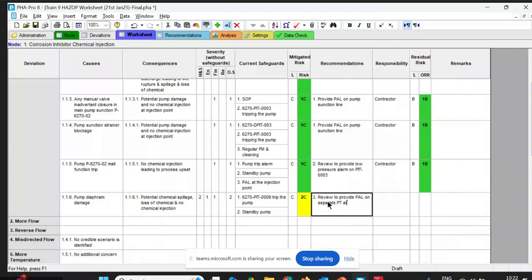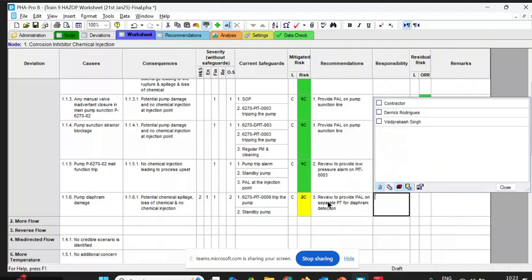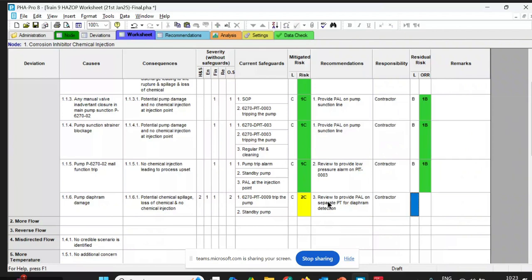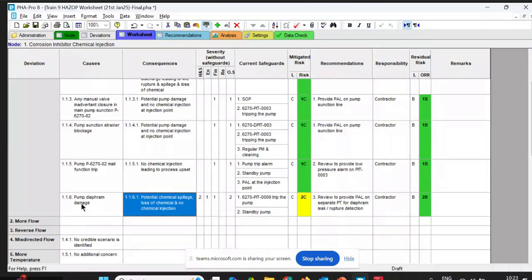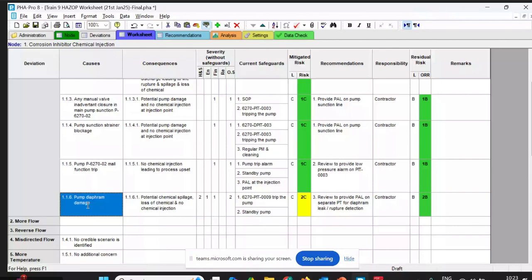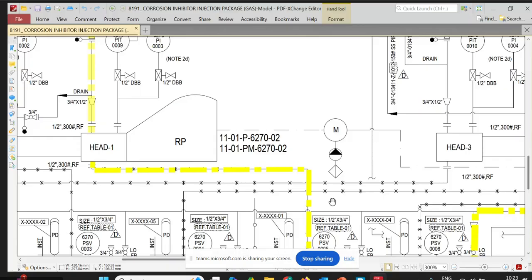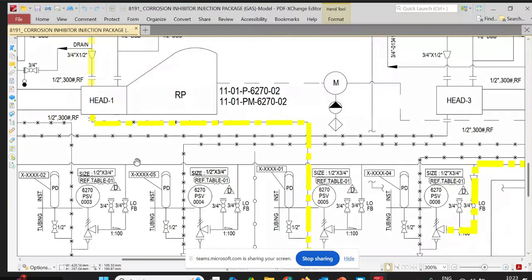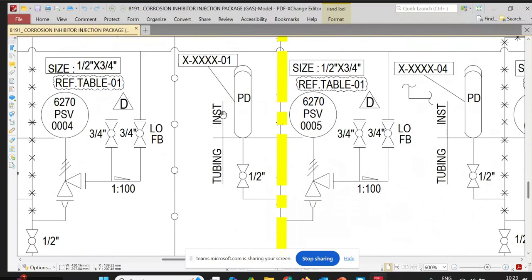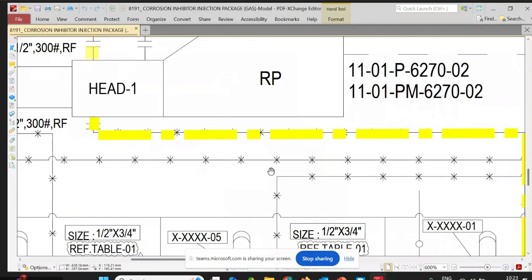PT for diaphragm, injection. Diaphragm rupture detection. Leak detection, yeah. Maybe in this case the diaphragm leak detection will not be helpful. For the other cases it may help, because I didn't have enough operator effective response time if the diaphragm is already ruptured. Yes, true. For the other cases, suction low or discharge high or something like that, it will be helpful. But for the diaphragm, I have no adequate operator response time.